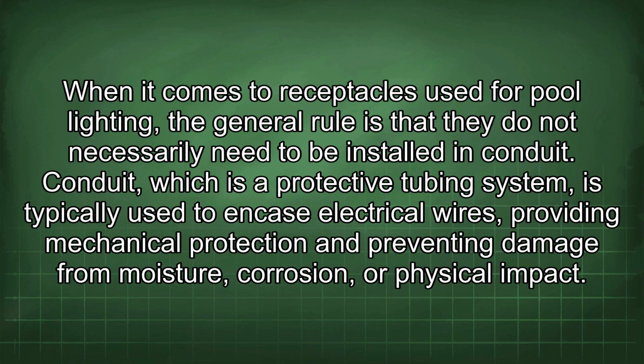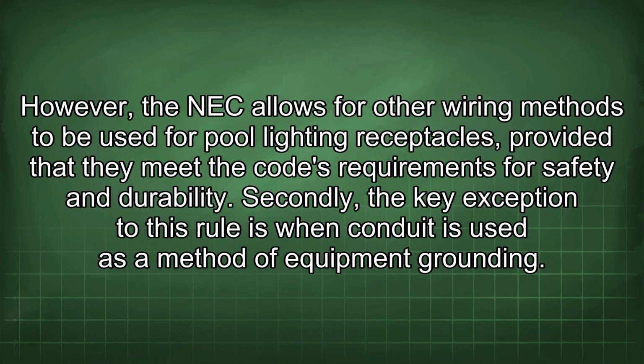When it comes to receptacles used for pool lighting, the general rule is that they do not necessarily need to be installed in conduit. Conduit, which is a protective tubing system, is typically used to encase electrical wires, providing mechanical protection and preventing damage from moisture, corrosion, or physical impact. However, the NEC allows for other wiring methods to be used for pool lighting receptacles, provided that they meet the code's requirements for safety and durability.